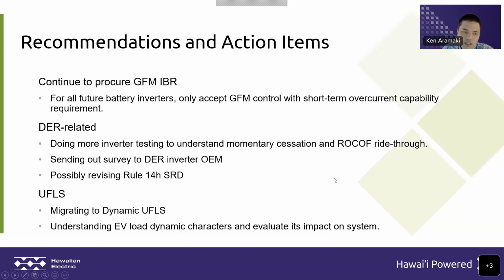And then also, because with under-frequency load shed you want to drop load, what we need to do in the future is understand what types of loads are out there or are going to be implemented, and see how we can address the UFLS functionality with these new loads. So for example, EV chargers might be a good way to add to the under-frequency load shed scheme, where in times of need for dropping load, maybe we can drop EV chargers for a short duration until the system can recover.